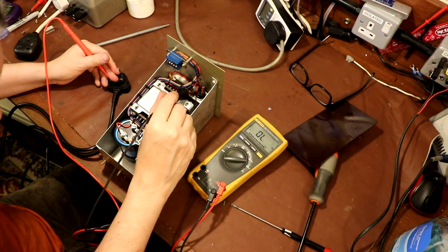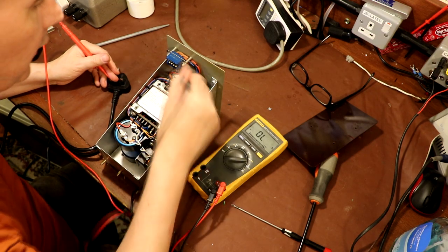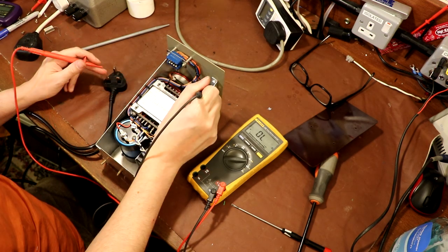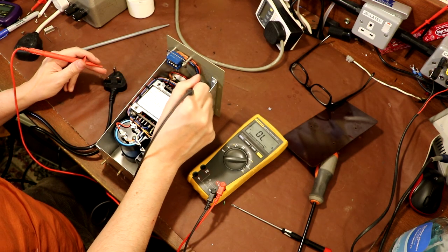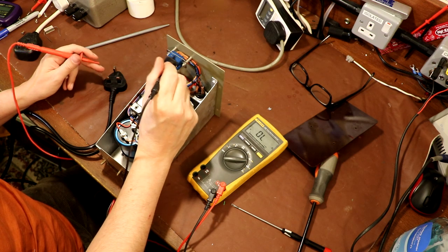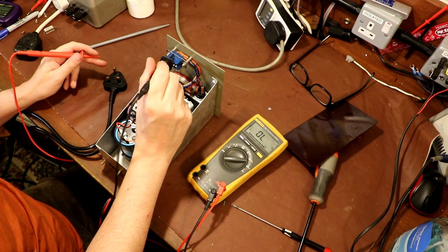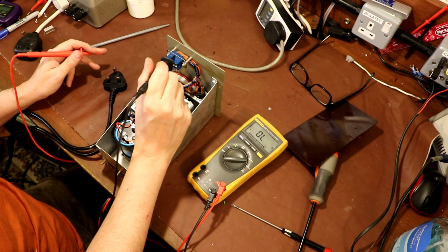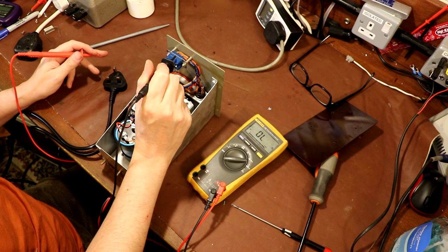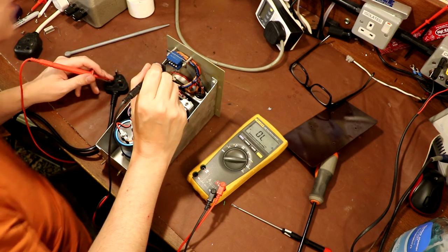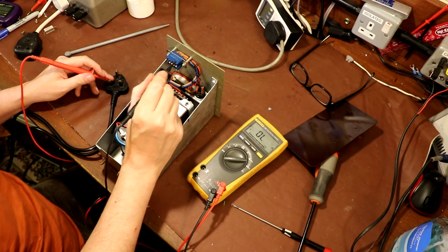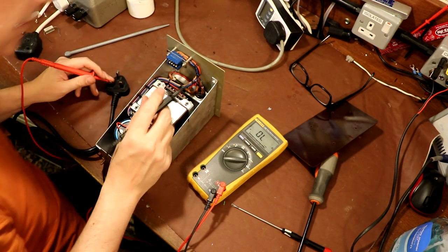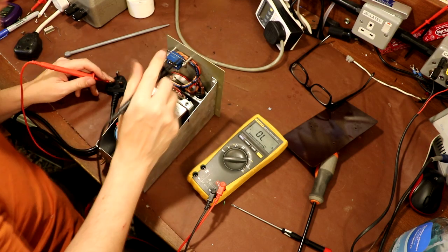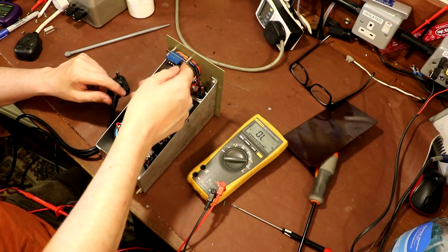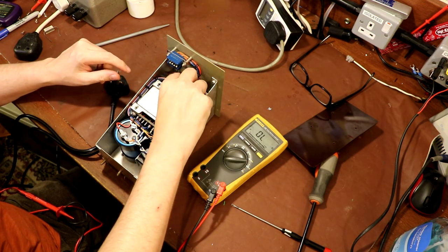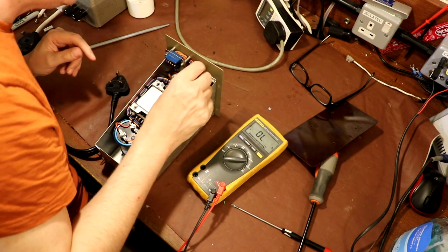Yep, got it to there. Comes out the back of the mains connector, and I think that goes into a fuse there. So what will happen here: the live wire comes out of this main socket on the back, goes through a fuse, and immediately goes up to this socket on the front. It's going to go from that socket to the front panel selector switch, I think, where the instrument will be powered on and off - or that's what I assume will happen. Then that mains power will return back, but I'm just wondering where it will return to - which of these wires does it return on? The problem is it's all beautifully loomed up, but because it's so beautifully loomed, it's very hard to actually trace out the wiring.